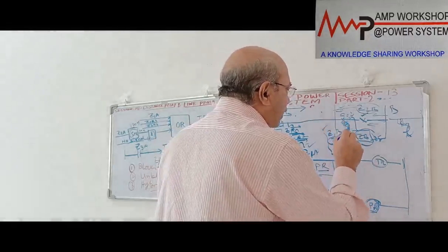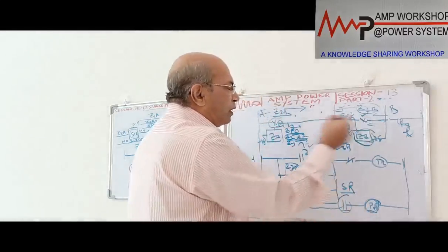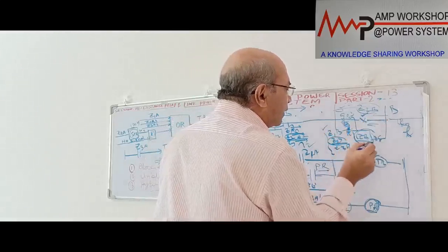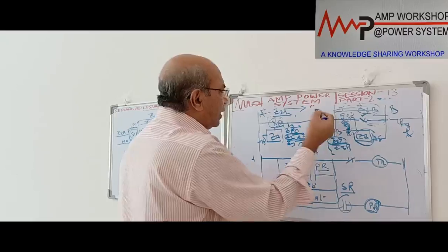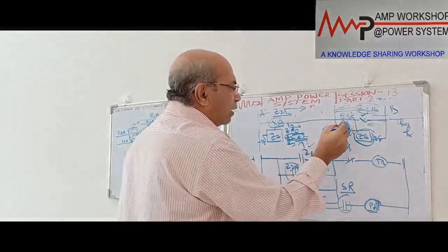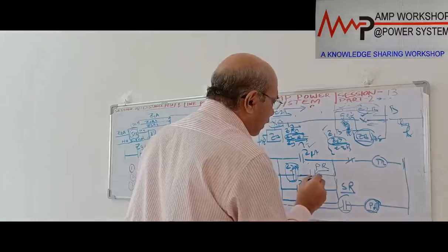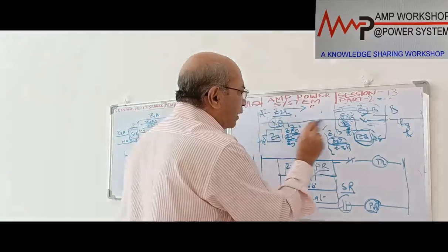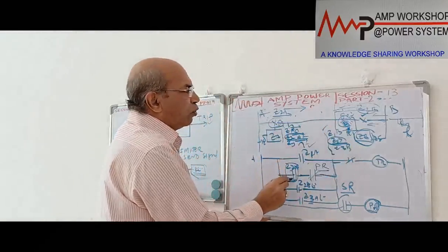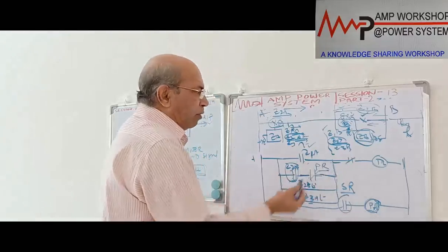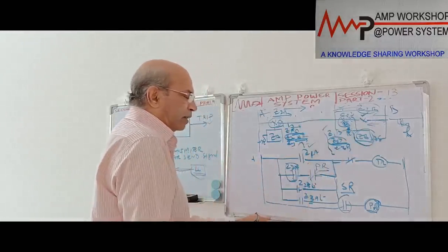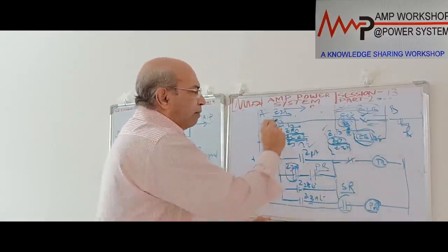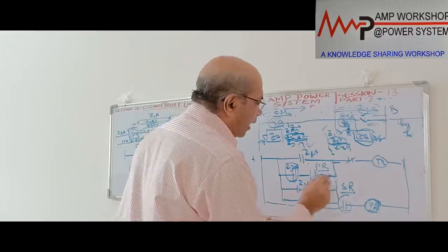But if the fault is within 90% from here within the line, then here Z2 has operated, and at the same time this end Z2 will be sending the signal to the other end because it is within the area. Then immediately the end zone fault, that fault within 90%, is tripping in the zone 1 area, with a 25 millisecond time required for the channel for the signal coming. So this end zone fault is cleared with the zone 1 time, and if none of them is working, then the normal time delay will be working.